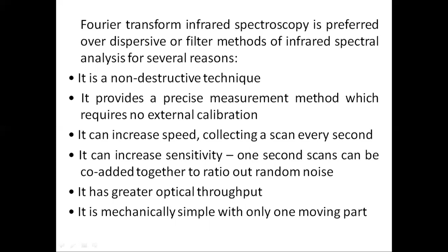Along with the advantages, there are a few minor disadvantages in FTIR compared to normal IR. Being single beam, it requires collecting a blank. You have to take a blank reading because the blank and sample are not taken simultaneously. So you have to take the blank and then take the readings for the sample.